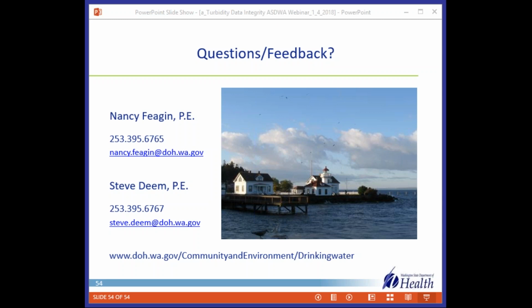Other things that may or may not be included in your service contract would be replacing the sampling tubing. And no matter if Hach does it or your staff do it, we think that all of these maintenance activities should be documented in an instrument-specific maintenance log. I can't remember if we talked about that, but lots of plants, especially the smaller plants, keep a general maintenance log of everything they do. Those are valuable, but those are difficult if you're trying to find out a specific question on a specific piece of equipment, like the last time the tubing was replaced.